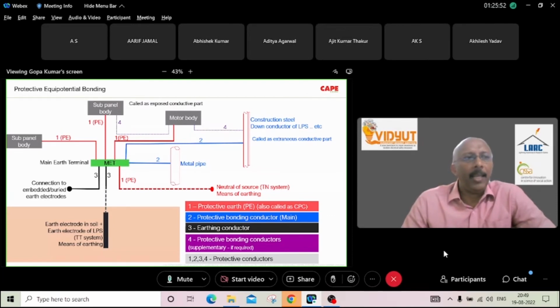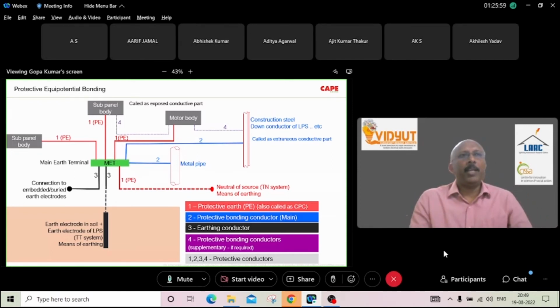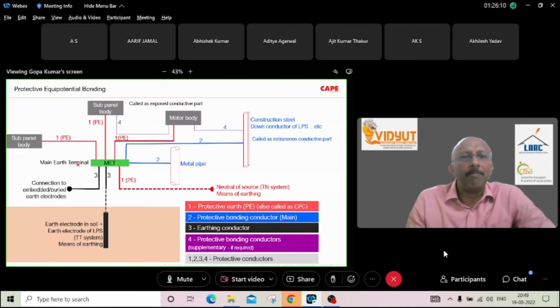In industrial areas, if you have a functional requirement, for example you have a lot of electronics or instrumentation systems, those instrumentation systems require functional earthing for proper working. But again, the functional earthing also must be connected to the protective equipotential bonding system. There is nothing called a separate earth electrode in soil. If you make a separate one, actually we are spoiling our electrical installation.